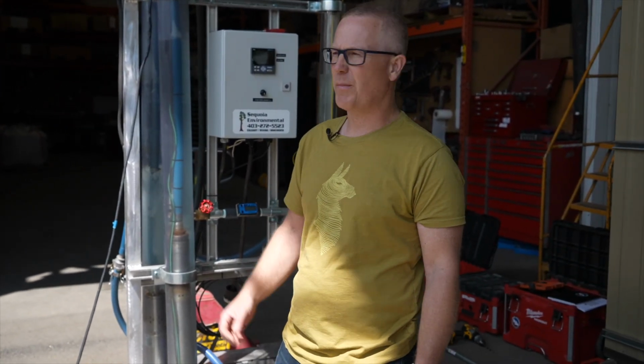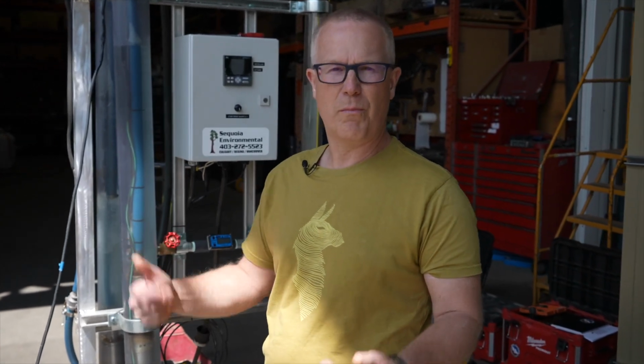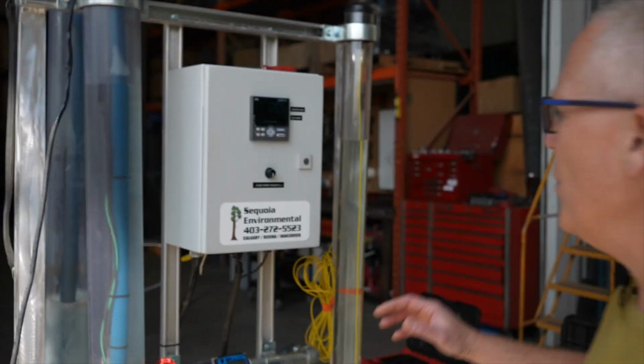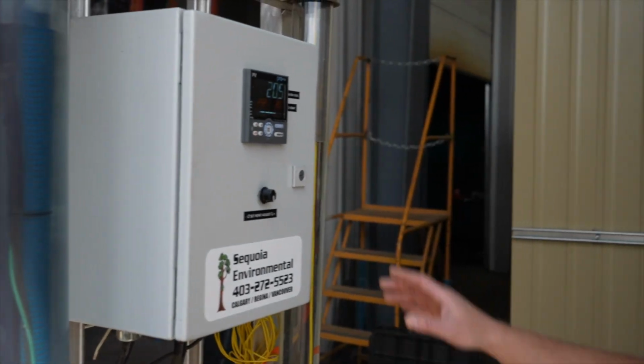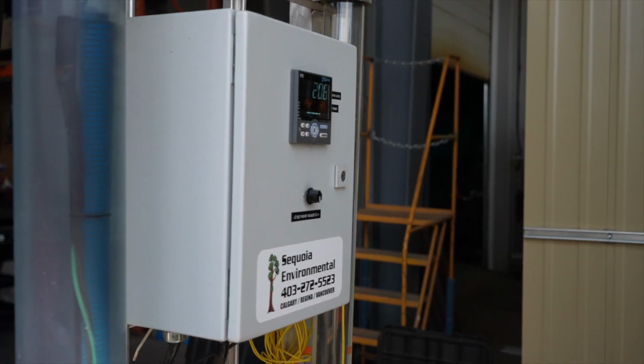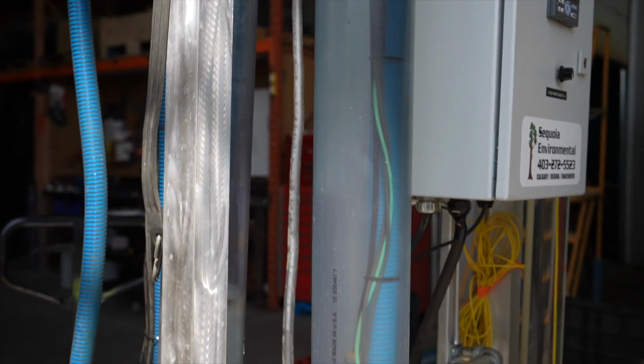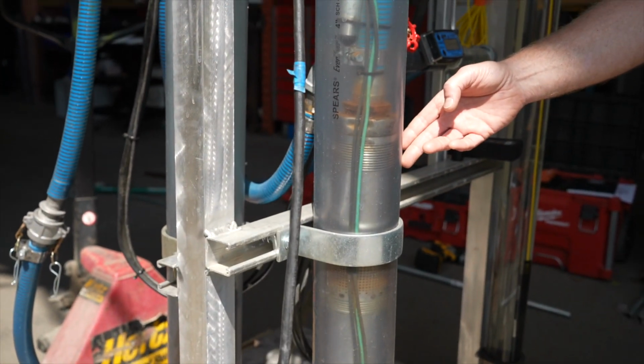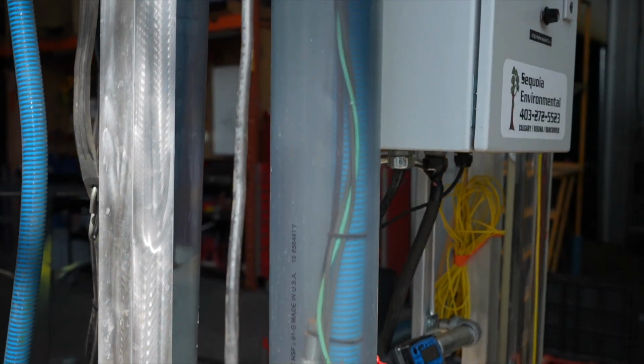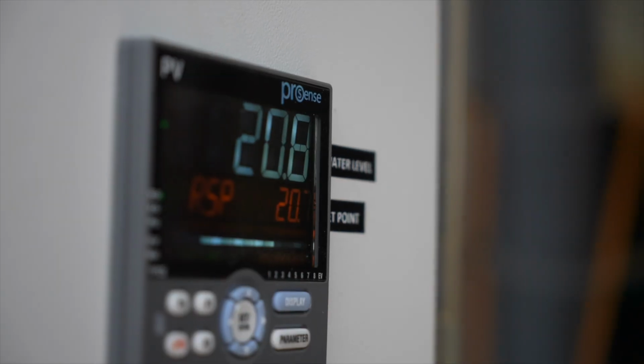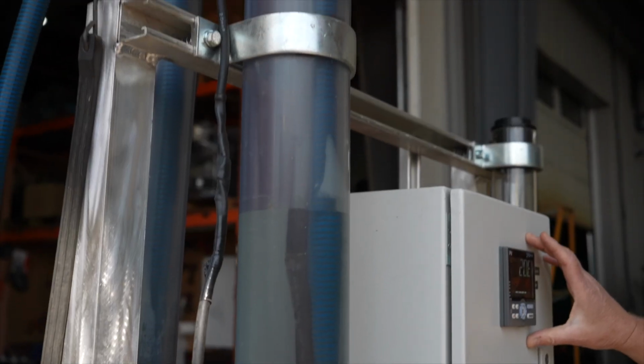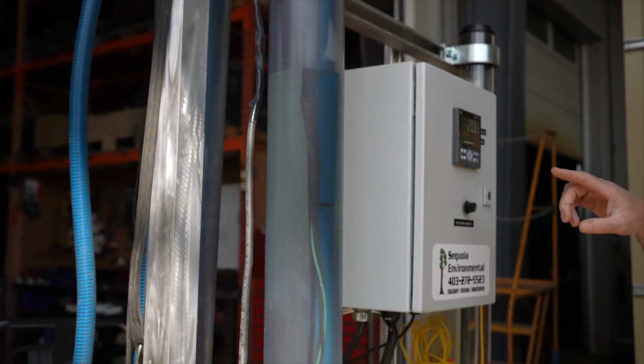This particular unit that's behind me enables you to put a pump into a groundwater recovery well, turn it on, and then you can either do a step test or you can do a continuous fluid flow test. And all of the computing program is done by Sequoia. How this works, and I currently have it running, is we have a standard Grundfos SQE pump that runs on a variable frequency. This system feeds back into the computer, and we've programmed it with a PID loop in order to control the flow, and then right up beside the pump you can see a transducer.